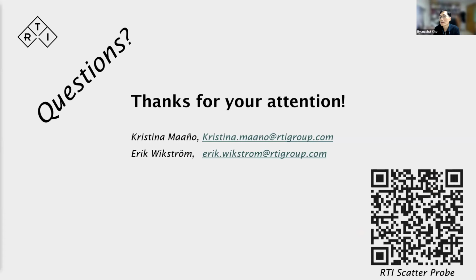I'm looking at the chat box, but actually there is no question. Only one question, but it is already answered by your talk. So the RTI scatter probe is based on solid state, right? It's not an ion chamber. Yes. And I guess it is a great breakthrough to flatten the energy dependency over all range of the diagnostic X-ray. So congratulations. Thank you very much.